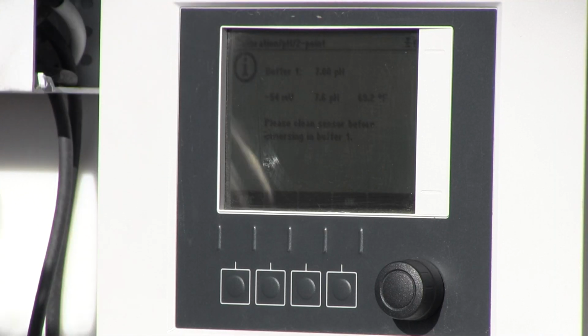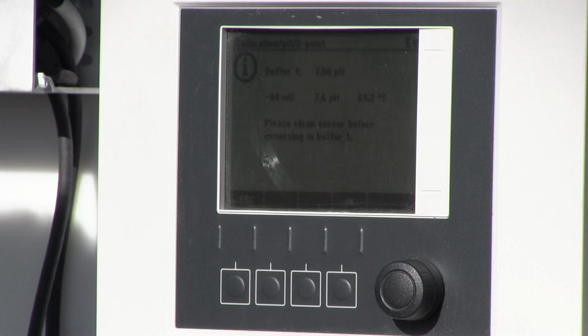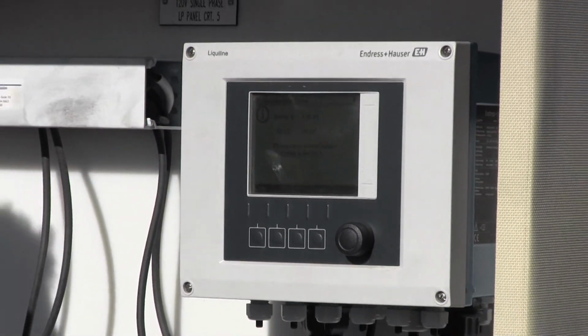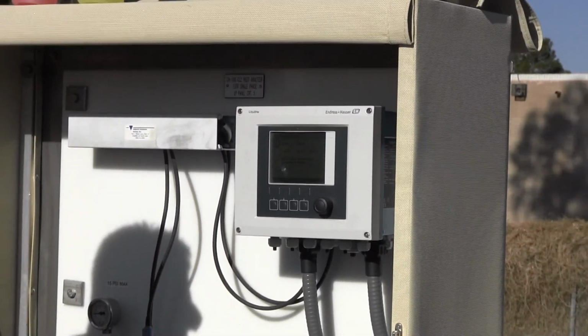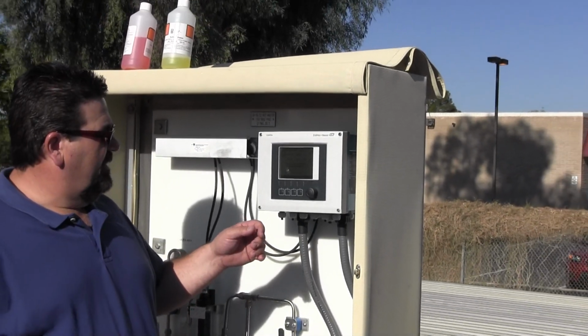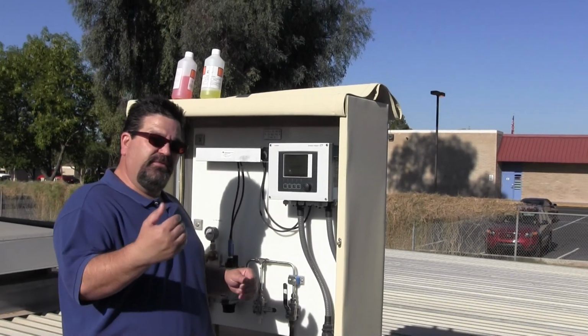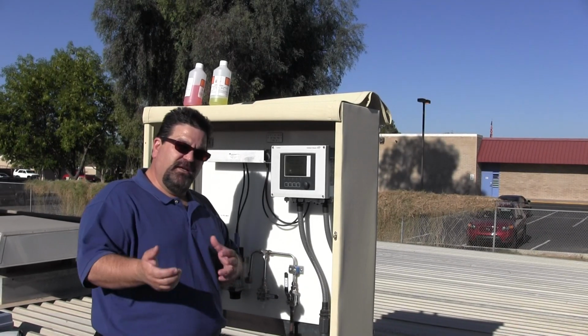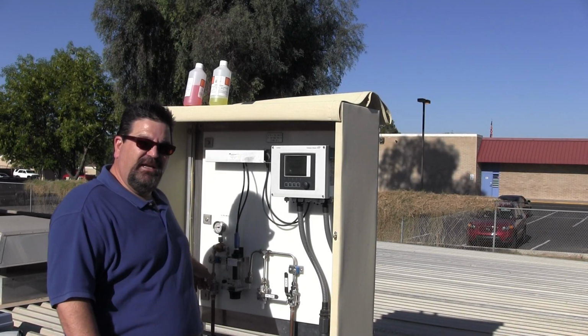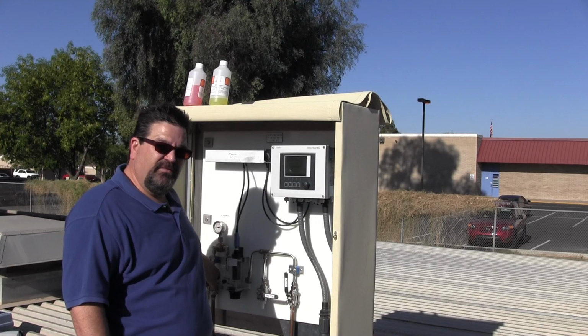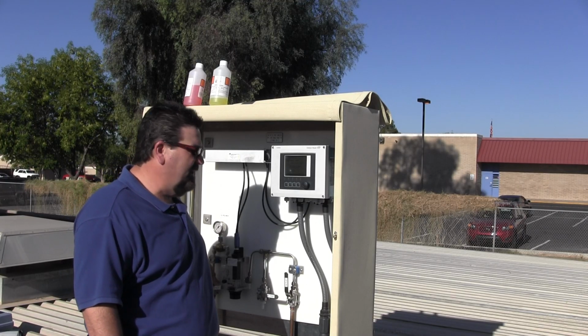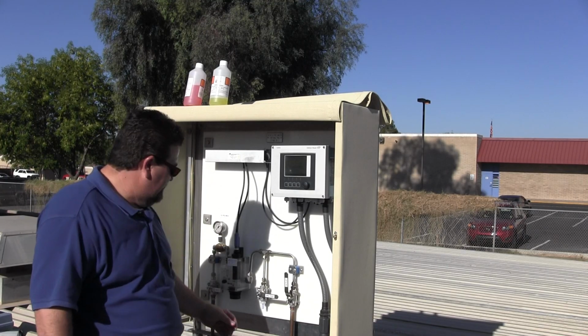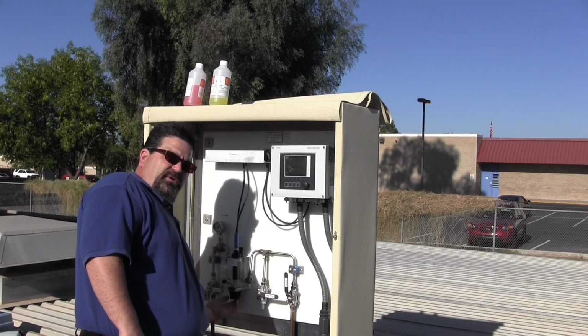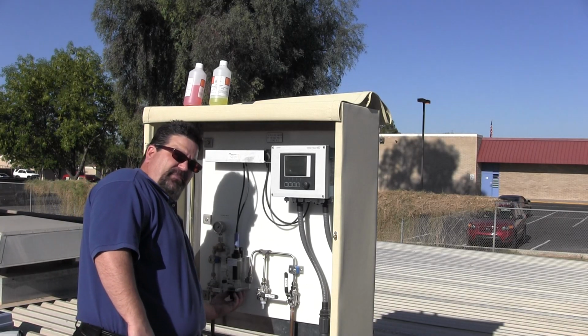There's an I with a circle around it for information. Prompts us to use buffer number 1 that has a 7 pH. Now when you stop the flow through the flow block and start the flow, pardon me, let me back up. Okay, I'm in a good spot. When you start and stop the flow through the flow block, please do it gently. We want to just simply, very easily close the valve that has our sample water coming in. The flow obviously drops off to 0. And we remove the calibration cup from the bottom of the flow block.